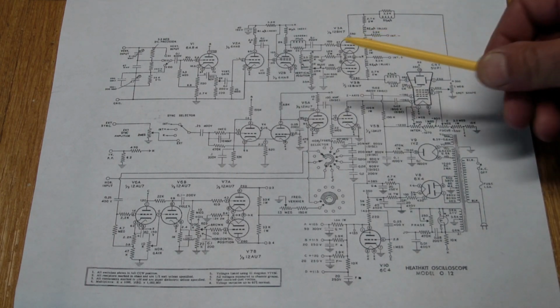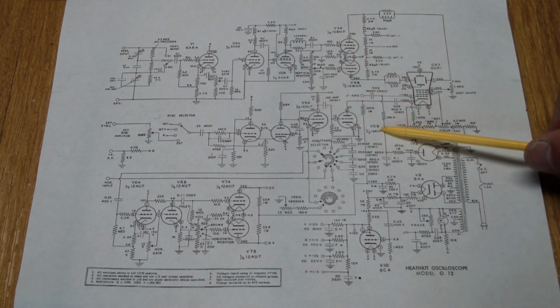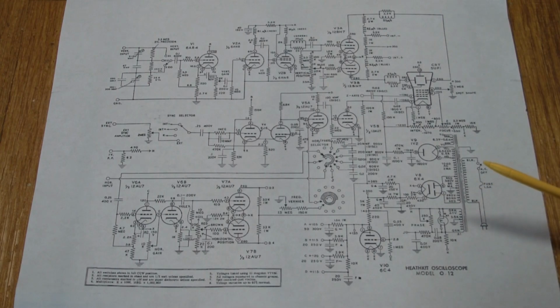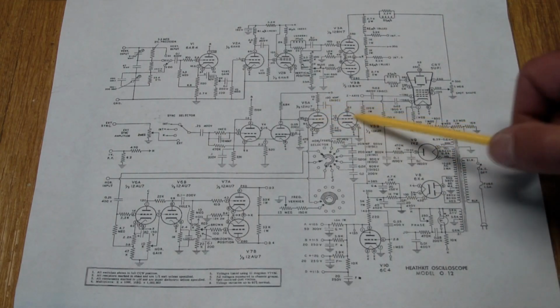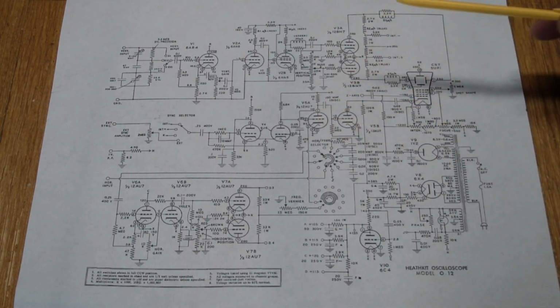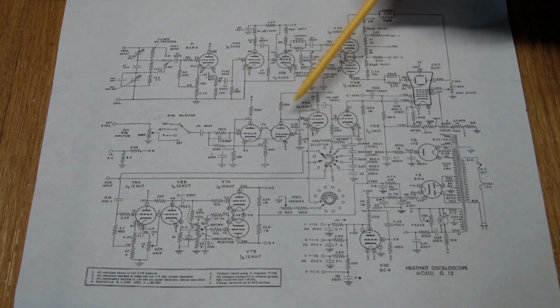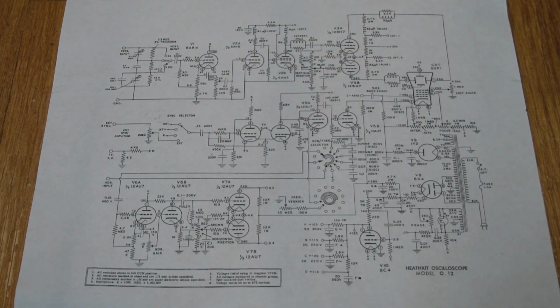V5, and here's V5A and V5B right here. And this tube was bad. What this would cause is, this is basically the sweep generator. So what that means is you would probably get a trace, you'd be able to do a vertical and a horizontal trace, but you would not have been able to show a signal because it would never sweep the screen.